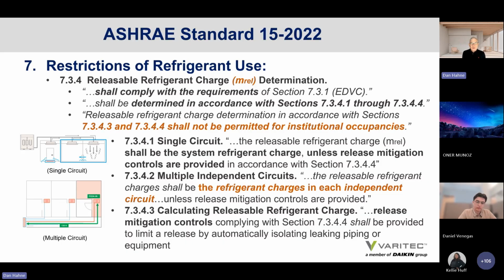Here's a very important term for defining how much A2L refrigerant can serve an occupied space. It is the releasable refrigerant charge. And how do you determine that? It's determined in compliance with the requirements of section 7.3.1, the effective dispersal volume charge, and shall be determined in accordance with sections 7.3.4.1 through 7.3.4.4. Releasable refrigerant charge determination will be in accordance with these sections. And there's language that supports the design of single circuit refrigerant systems.